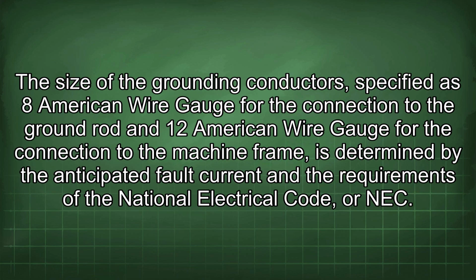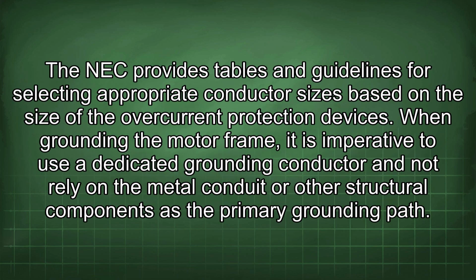The size of the grounding conductors, specified as 8 American wire gauge for the connection to the ground rod and 12 American wire gauge for the connection to the machine frame, is determined by the anticipated fault current and the requirements of the National Electrical Code, or NEC. The NEC provides tables and guidelines for selecting appropriate conductor sizes based on the size of the overcurrent protection devices.